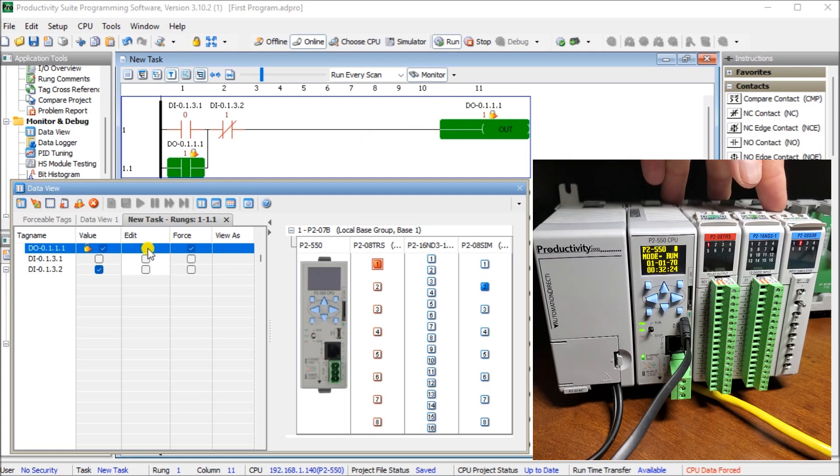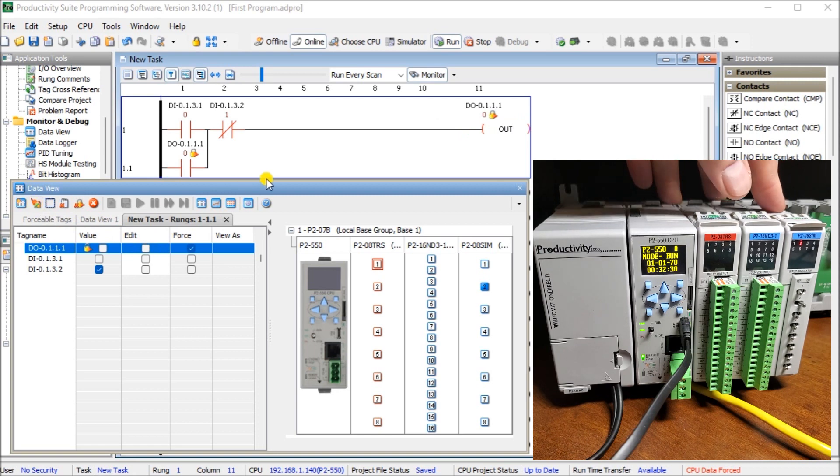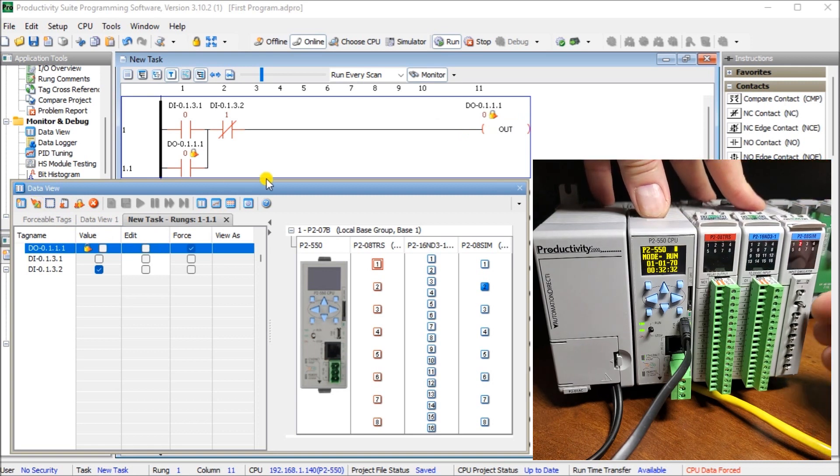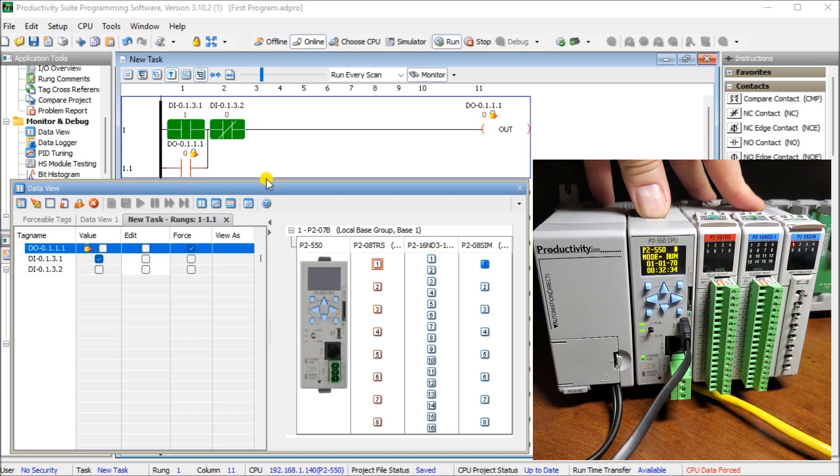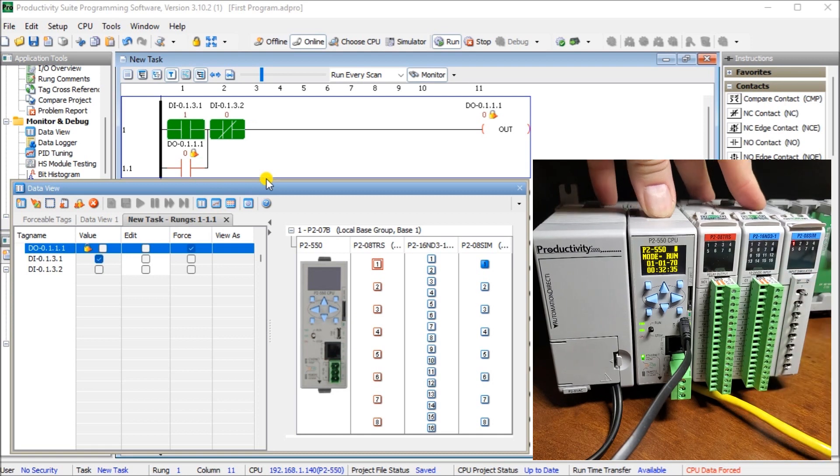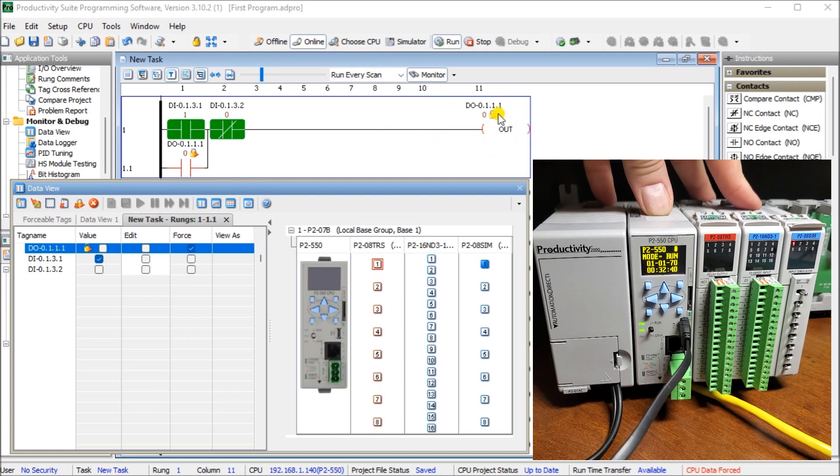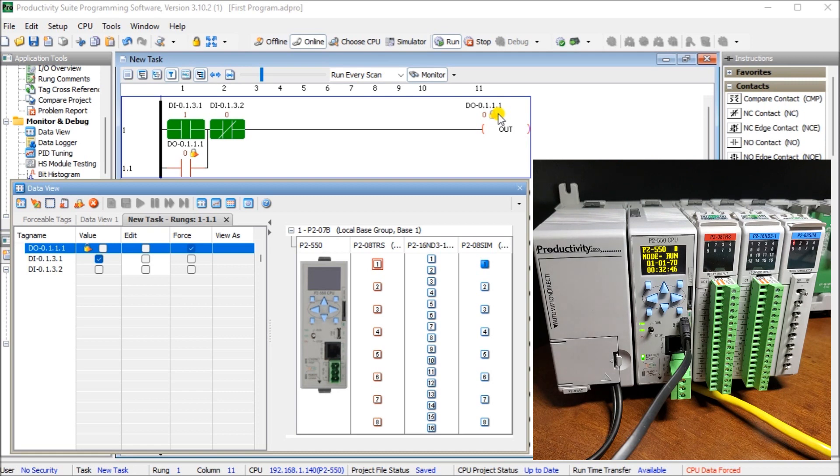Similarly. If I were to edit that. Turn it off. And force it. It turns it off. And I can then. Try turning it on. And my output does not turn on. So if you see this. It means that your logic. And your PLC program. Is not being solved. And remember. Our logic solved from left to right. Top to bottom.